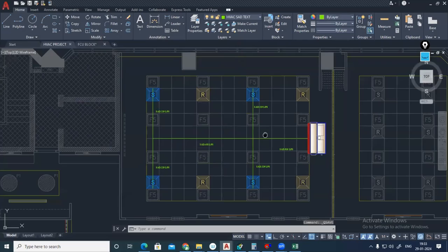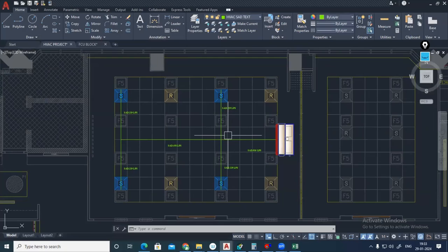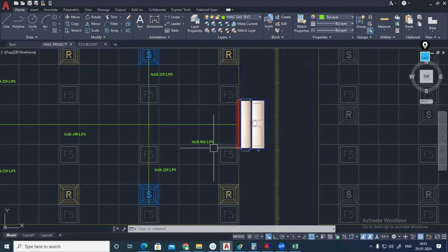Okay, now I need to size it. As you know, I'm having 1.2 meter of false ceiling. I will be trying for aspect ratio 1 duct here. Aspect ratio 1. But acoustic insulation, I will consider only in the starting. Other branches, I will not consider it. 916 liter per second. Let me select the duct sizer.